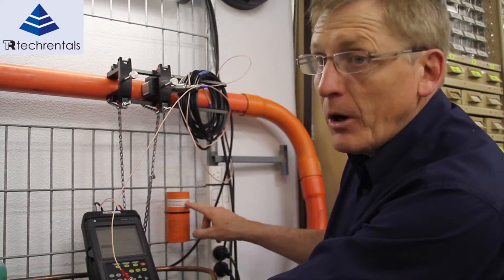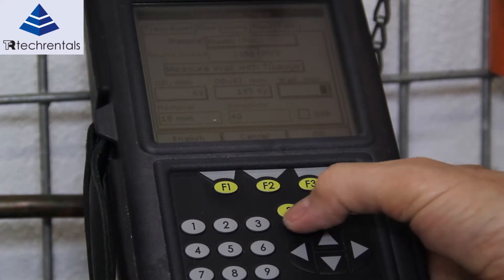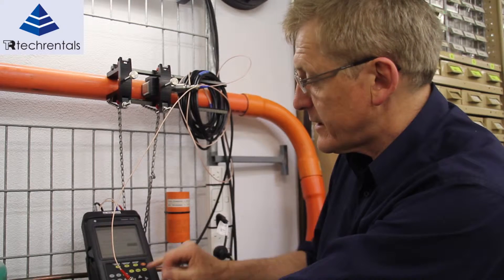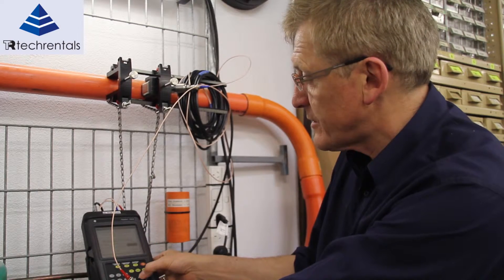Now, in this case we're using PVC pipe, the outer diameter of the PVC pipe is 63mm, the wall thickness is 4mm. It gives you the outer diameter times pi, so you can actually confirm that. You'd usually get these out of the tables. If you happen to have a DIN pipe you can select this particular schedule from the bottom which makes it quite simple.